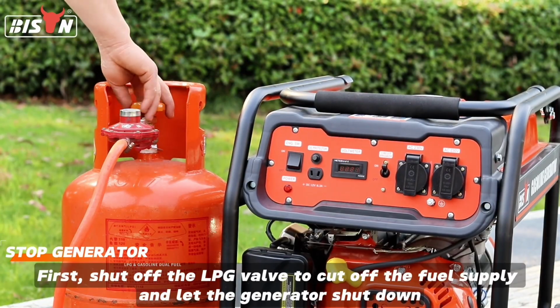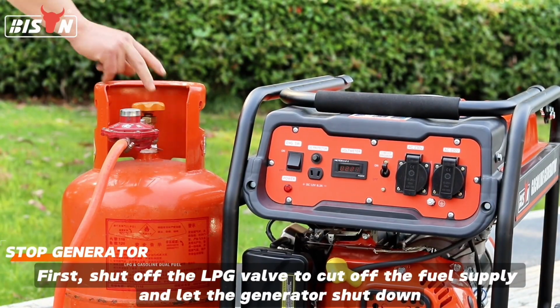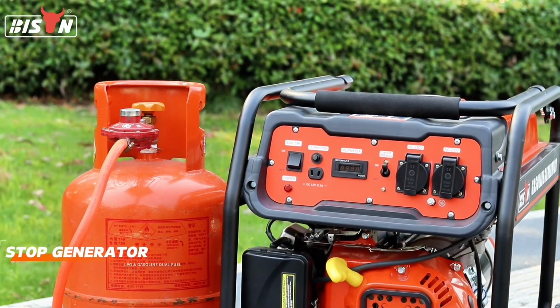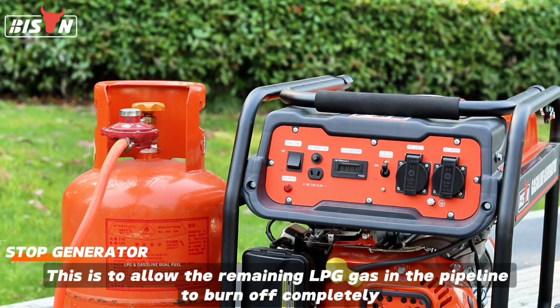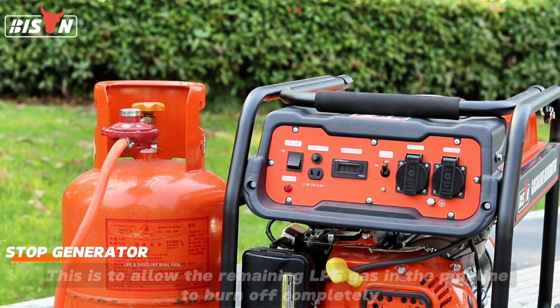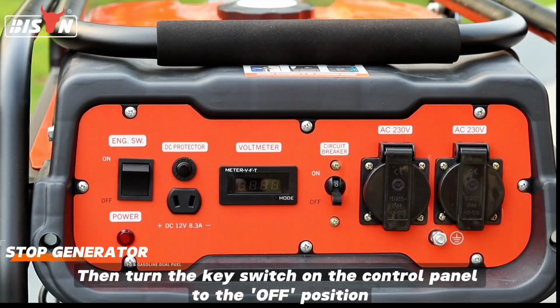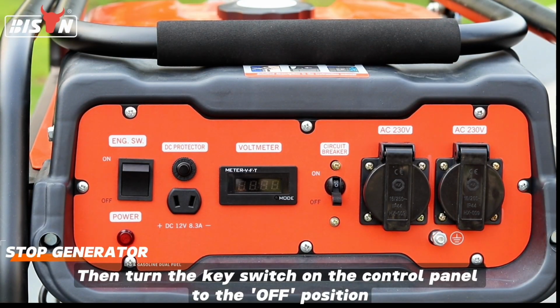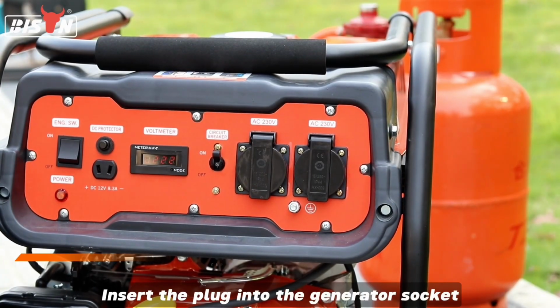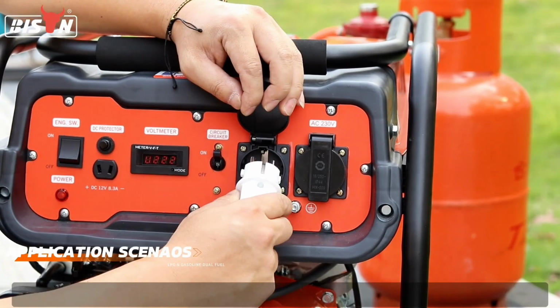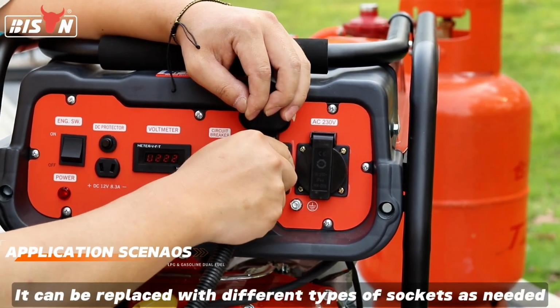First, shut off the LPG valve to cut off the fuel supply and let the generator shut down. This is to allow the remaining LPG gas in the pipeline to burn off completely. Then turn the key switch on the control panel to the OFF position. Insert the plug into the generator socket. It can be replaced with different types of sockets as needed.